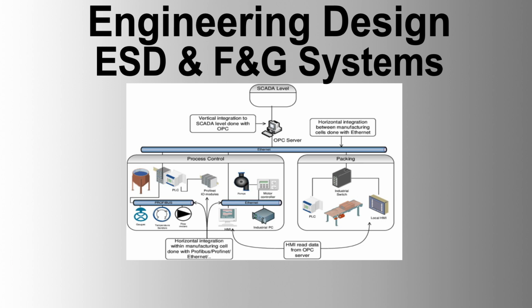4. Specific functional requirements. Early detection of hazardous conditions and initiation of appropriate alarms. Implementation of plant shutdowns and blowdowns as required. Isolation of hazard sources and ignition sources. Activation of extinguishant systems and visual and audible alarms throughout the facility. Continuous monitoring and reporting of system status to operators.